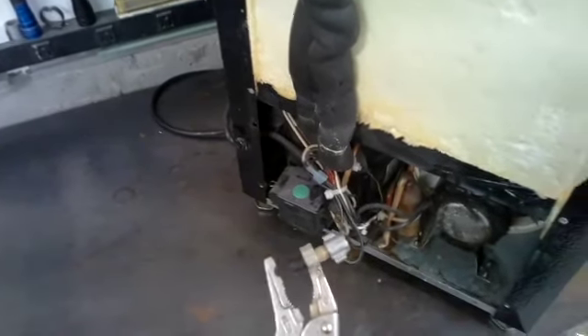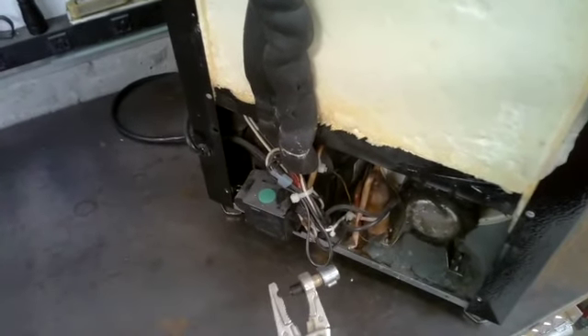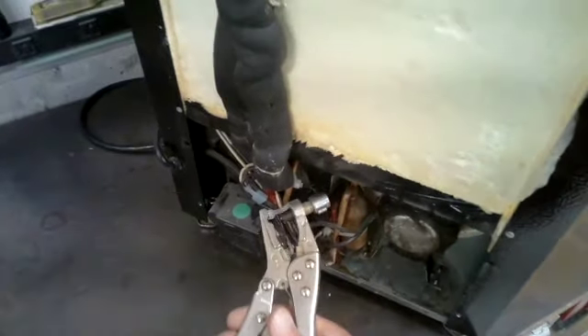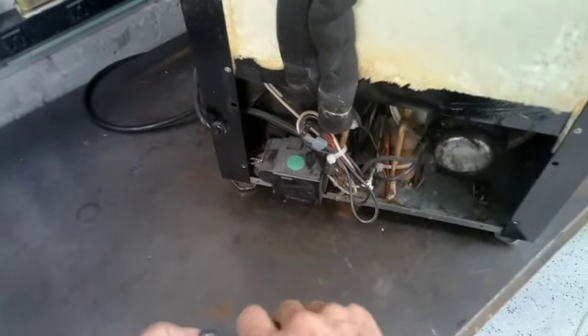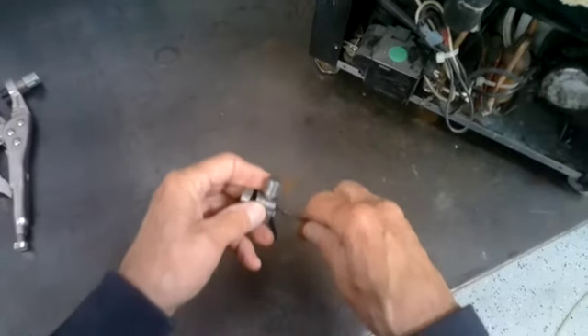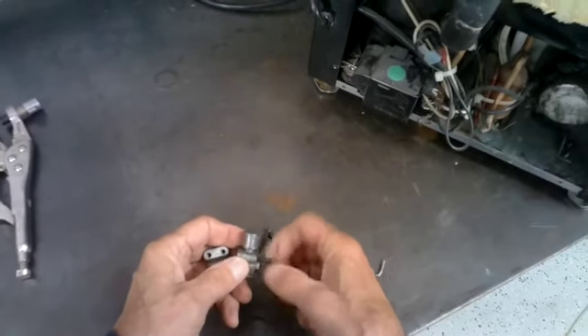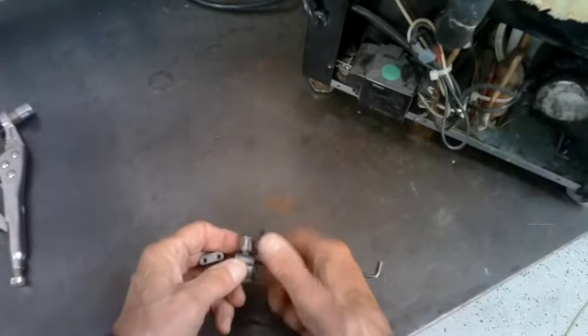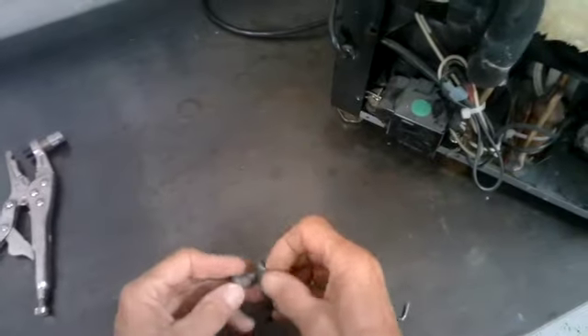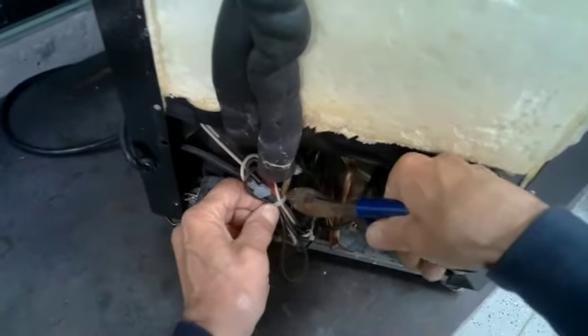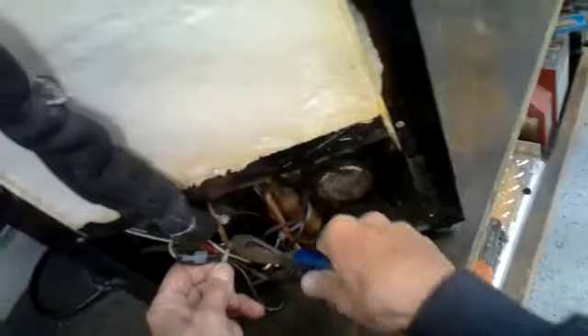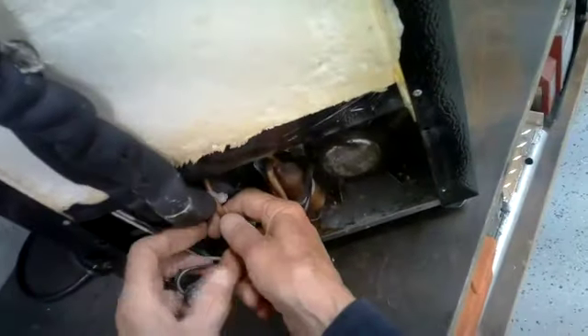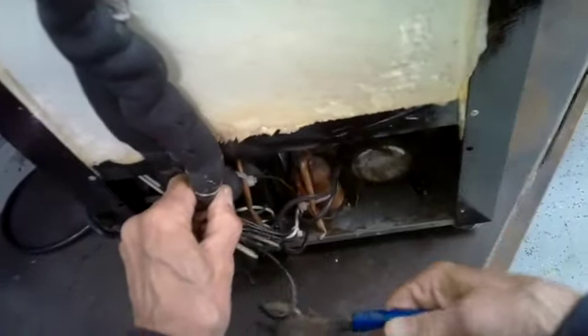This thing here, I don't have anything really good to say about this tool. I would imagine it works better on larger tubing, but on 1/4 inch tubing, it doesn't work for me. It leaks. And the whole purpose of using it is so you don't leak any Freon out into the air. So that's the way it is. So we're going to put this Supco tap valve on here. Okay. That out of the way so we can get it in here. There's another one here. Cable tie.